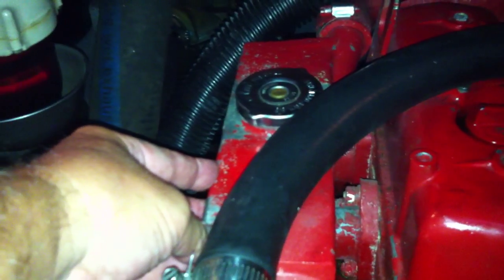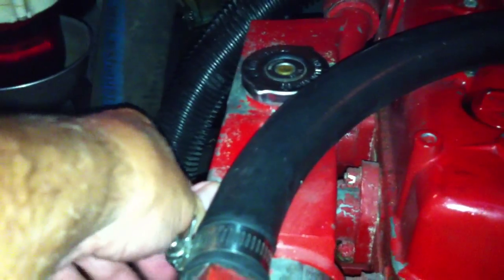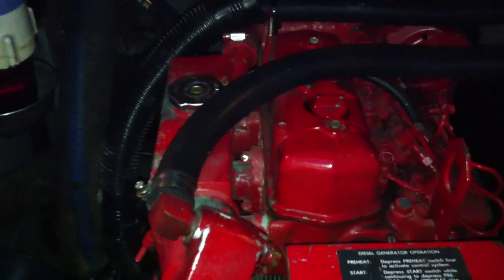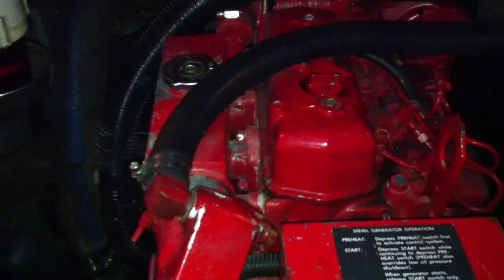This particular generator and the engines have a primary cooling side, which is almost like the radiator on your car, except there's no fan, no air cooling here - we're cooling with water. This reservoir and the engine block have antifreeze in them, which runs through a heat exchanger down below, which you can't really see from here. One side is the coolant side from the primary side of the engine, and the other side of that heat exchanger is the raw water coming in from the sea, cooling the heat exchanger, cooling the antifreeze, and then letting it go back into the engine to keep it cool. So that little rubber impeller is what moves water from the sea into the boat, through the heat exchanger, and back out again.